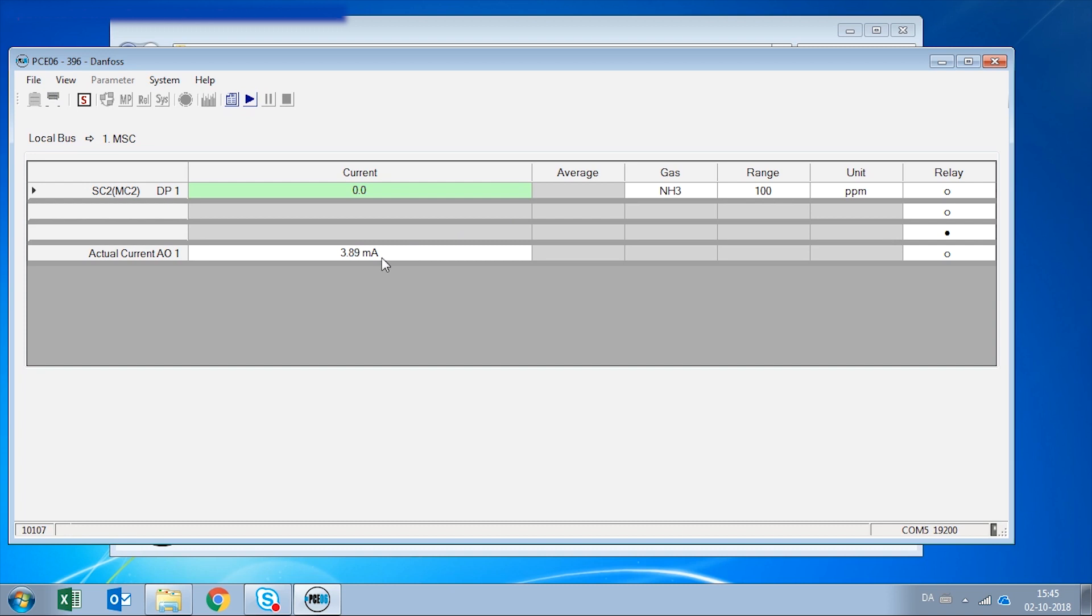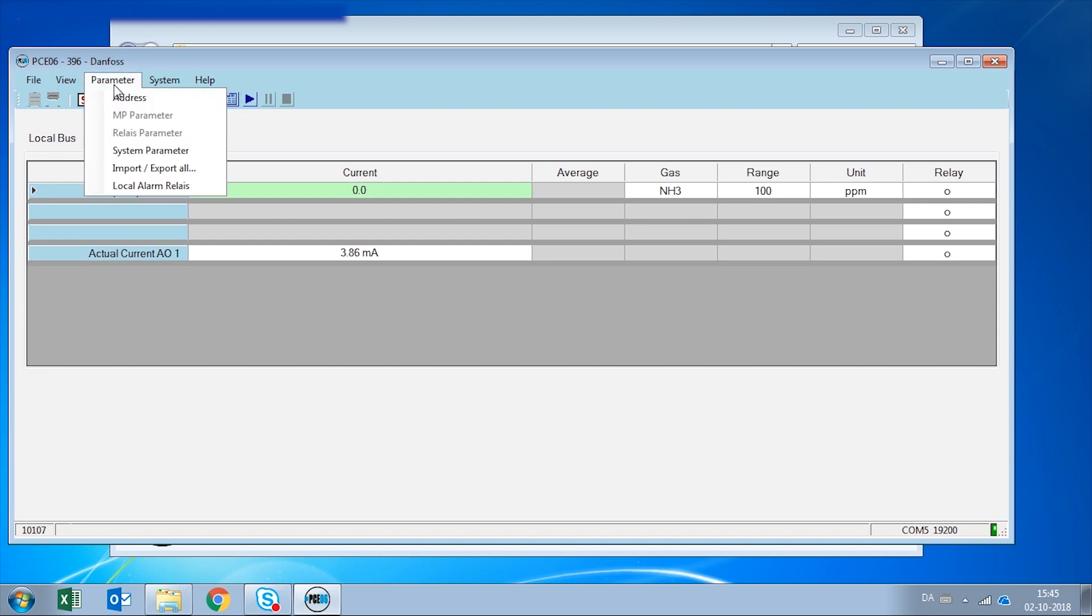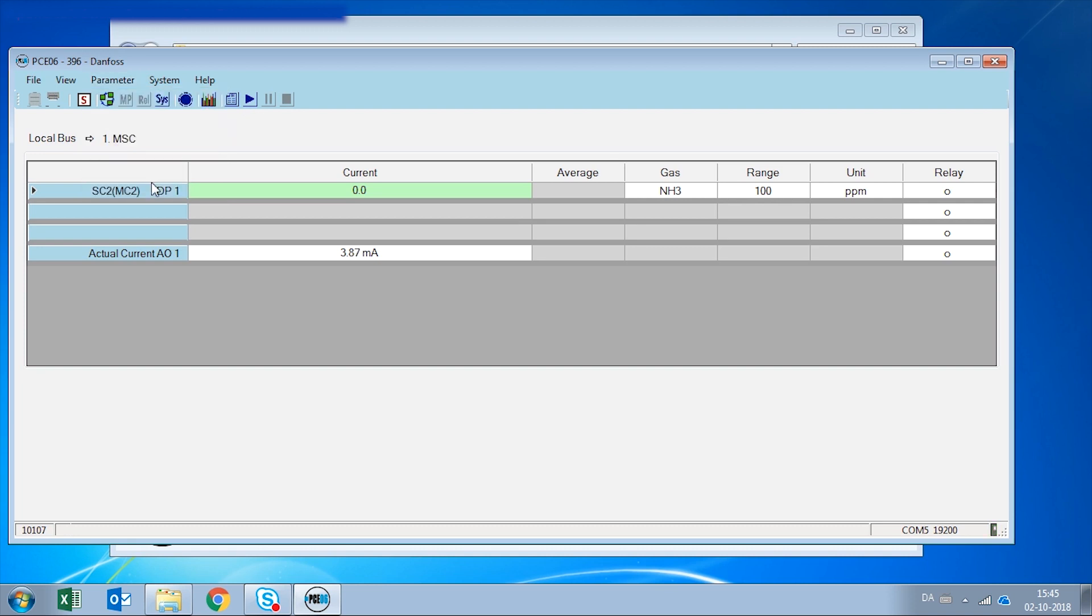Now we are going to put the digital gas detector into service mode and for that we are going to click this button on the top left that is an S. The moment we click it, the gas detection goes into service mode and we are allowed to see the other buttons that are here on the right. We're going to go to parameter and click local alarm relays in order to activate all different options.